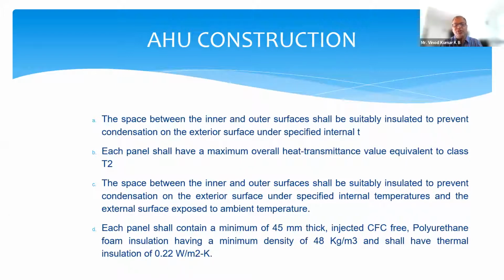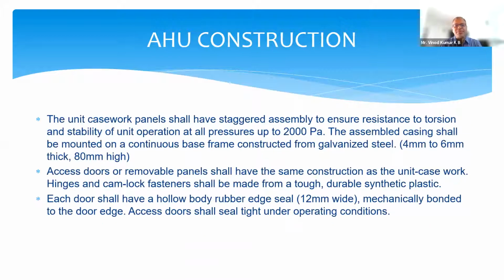It's just cooling, cooling, cooling. That's it. But we should not be talking the same category of saying cooling in my theater, cooling in my ICU. No, it is air conditioning where you have the temperature, your humidity, the air filtration, and above all, the positive pressure that you maintain. So the whole sequence, once I finish the specifications of the AHU, you will understand how important it is for you to select your air handlers of this construction.